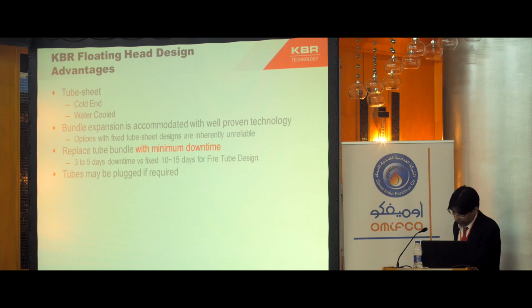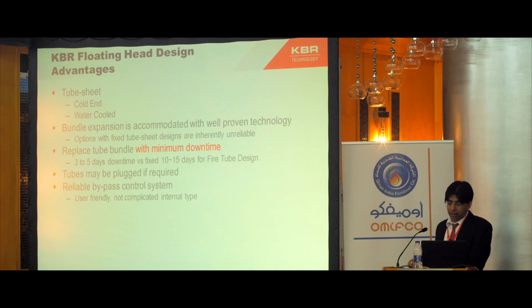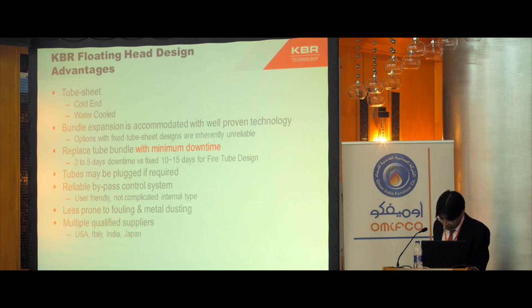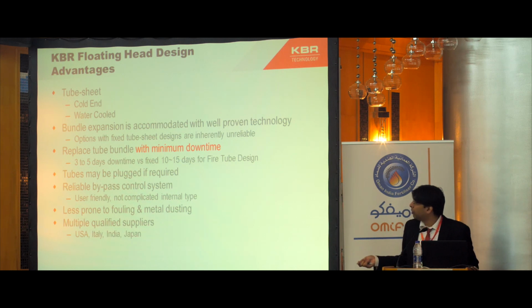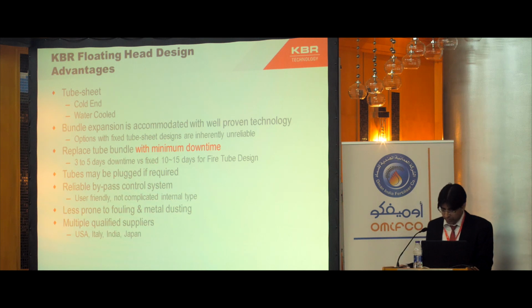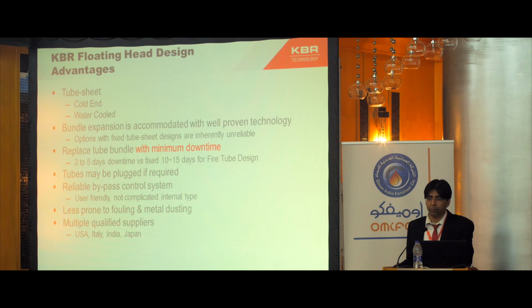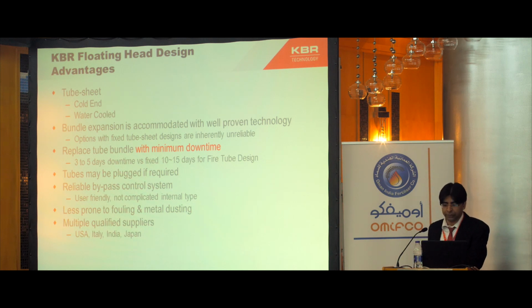Individual tubes may be plugged if required. Since the control valves are in the relatively cooler process gas piping, the valve design is conventional and reliable. So there is a reliable bypass control system, not an internal type. It is less prone to fouling and metal dusting. The design also allows for competitive bidding and takes advantage of global economic conditions with multiple qualified vendors in USA, Italy, India, Japan. The major advantage with this floating head boiler is it can be replaced within 3 to 5 days. We can provide a design which will not fail. We can provide a design which is easy to fix.